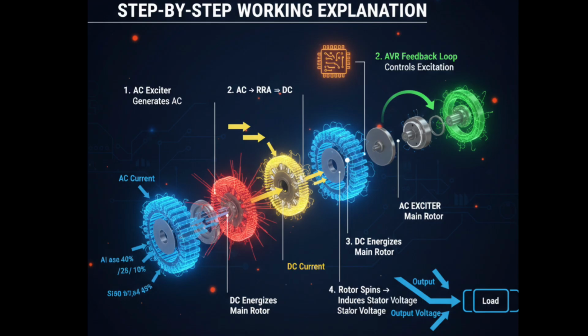Step 3. This DC is then fed into the main rotor field winding, which creates a rotating magnetic field. Observe the red magnetic flux lines in the slide. These lines move in synchronization with the rotor rotation and induce voltage in the stator. Step 4. The stator windings pick up this magnetic flux, generating three-phase AC output. The output voltage is sensed by the AVR, which continuously adjusts the rotor field to maintain a constant voltage despite load fluctuations.